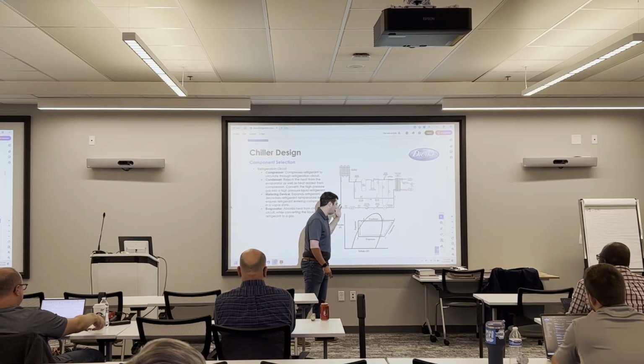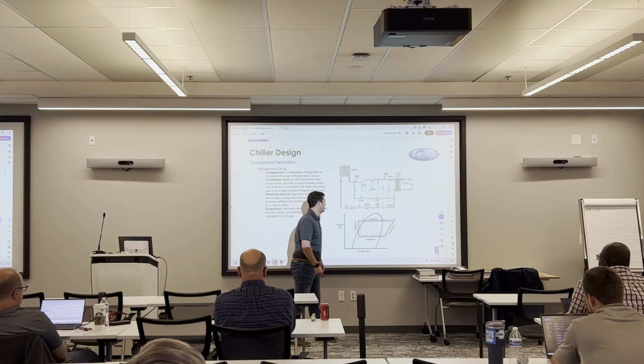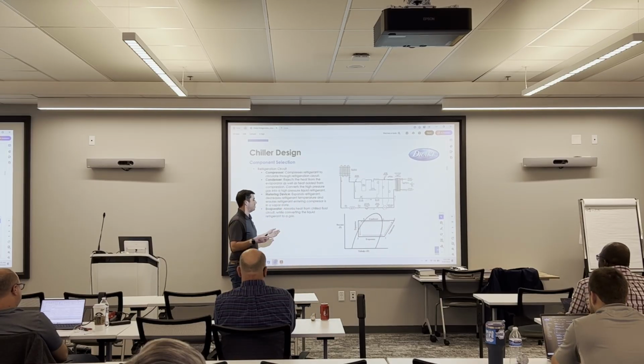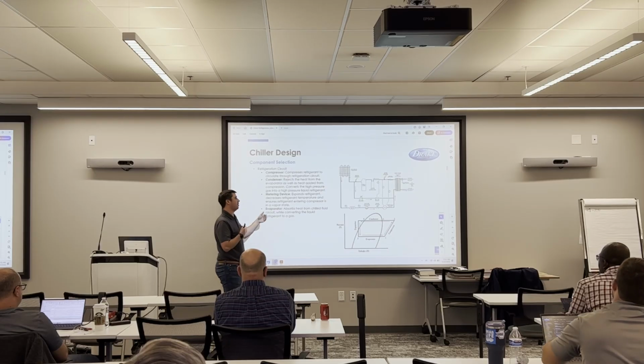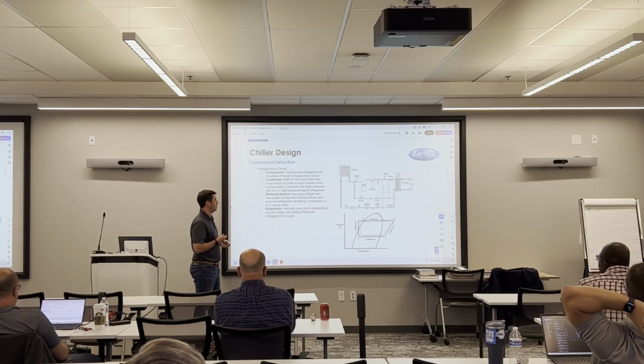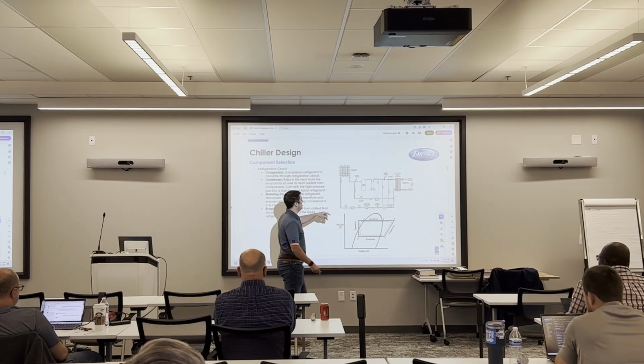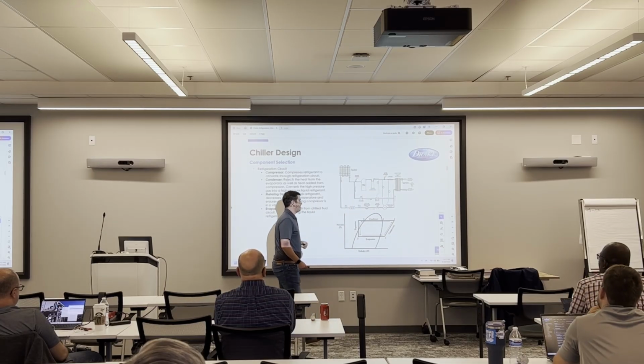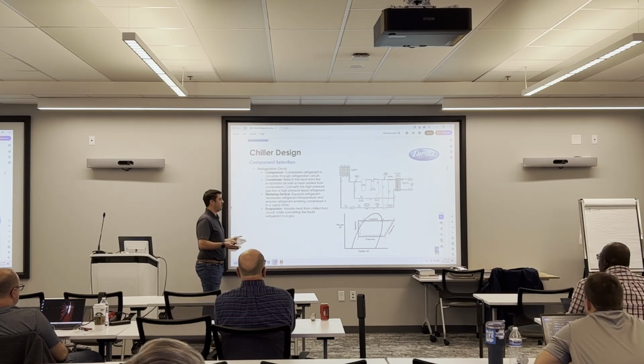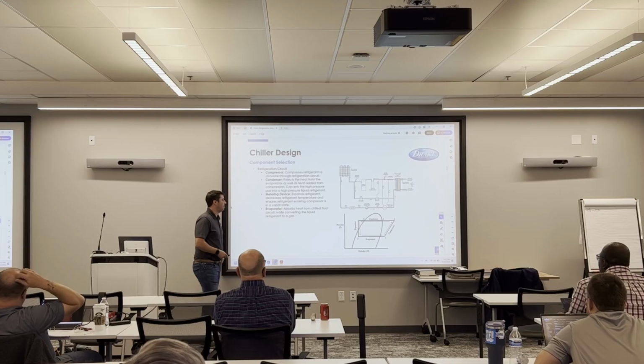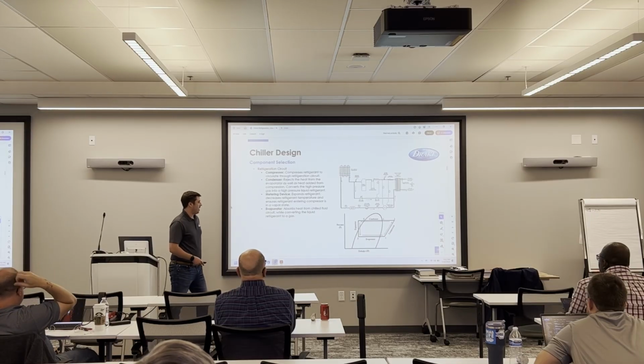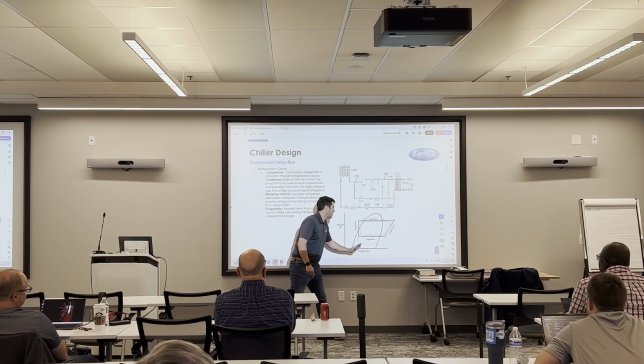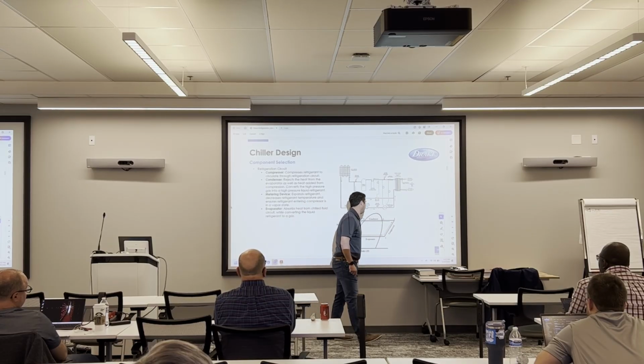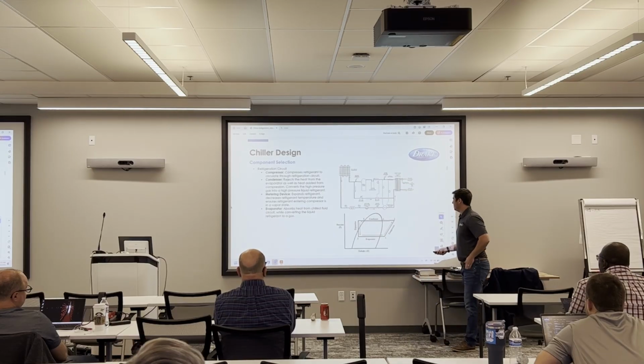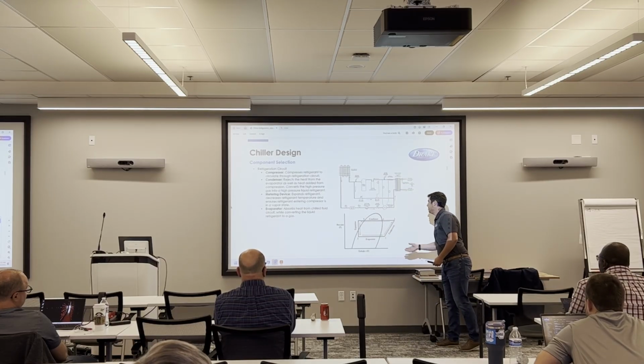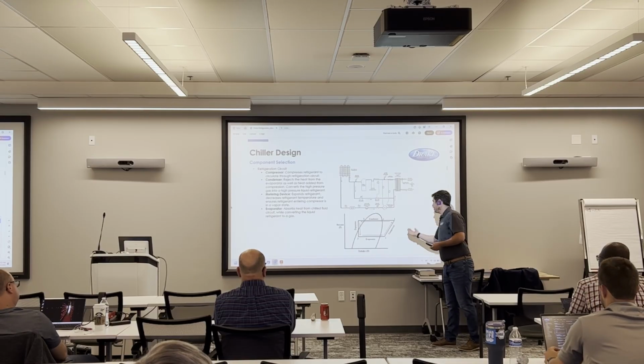Let's just say at a given pressure, at this point right here, the temperature of the refrigerant is 50 degrees. We'll call that our saturated suction temperature. It's the point where the refrigerant's about to convert to its gas phase. Then we'll physically measure the suction temperature, and let's say our suction temperature at that point was 60 degrees. So 60 minus 50, we've got about 10 degrees of superheat. Life is good. The compressor is going to take that low pressure gas and compress it. You can see the build of pressure here. And again, the compressor's adding more heat to the system, so it makes sense to get farther away from the curve because you're adding additional superheat while pressurizing the refrigerant.